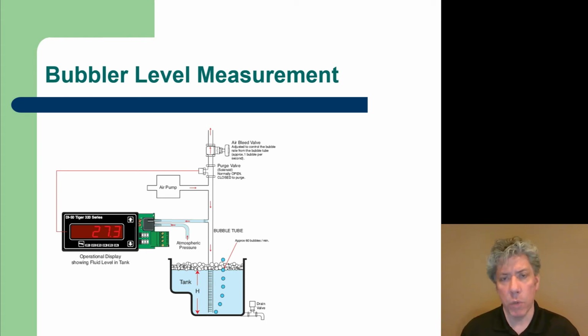And the way this system works is based on fluid statics. If you know the equation, pressure equals rho g h, or essentially that the pressure at the bottom of the fluid is largest, it's larger than the pressure less shallow in the fluid. That's what's being done here. So there's an air pump, and this air pump is not like an air compressor that's putting out a large volume of flow. It's just putting out a very small volume of flow. And you set the air bleed valve at the top in order to get just bubbles coming out, about 1 per second or so when the tank is full.